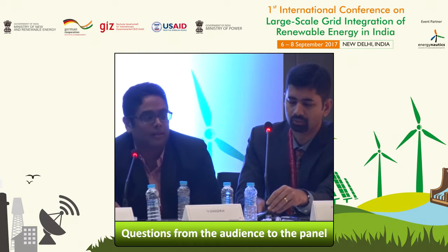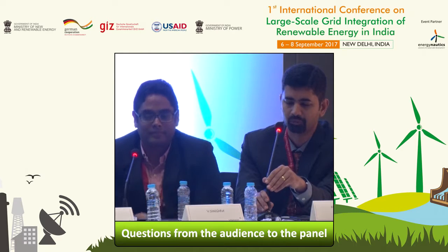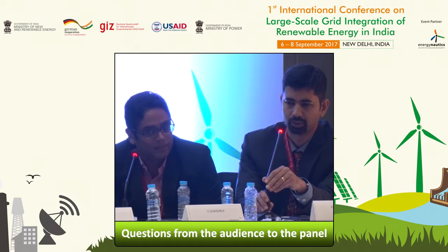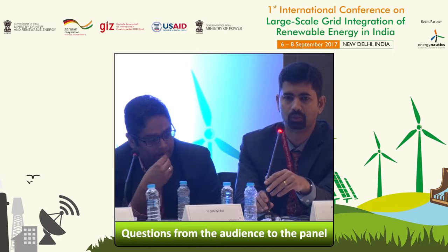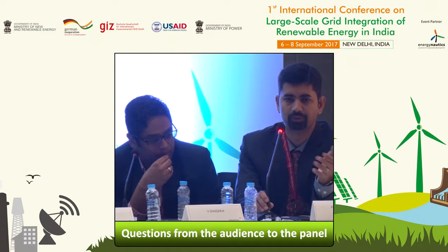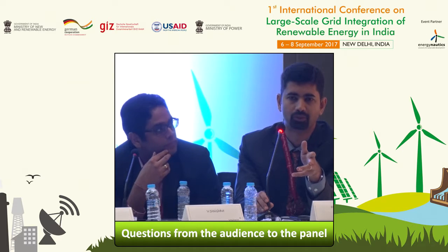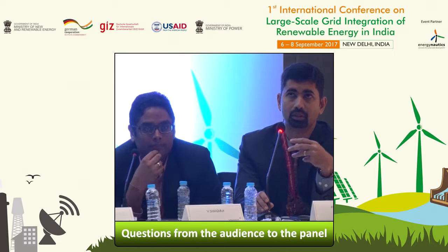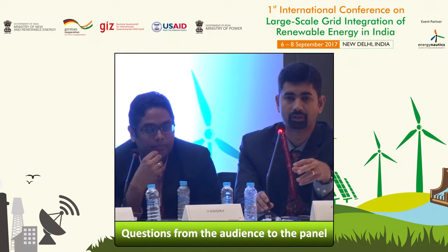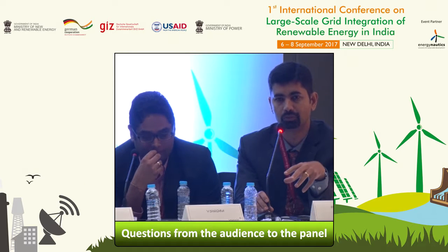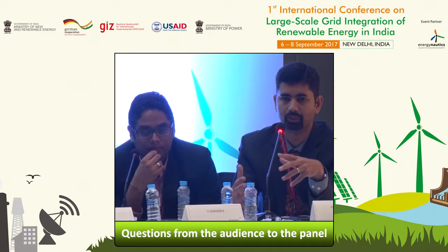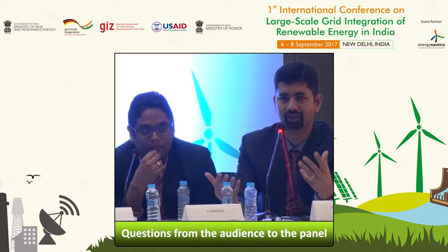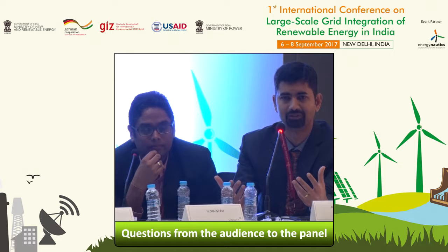Yeah, there's actually a regulatory requirement, I'm not exactly sure who it applies to, but I think it applies to MISO as a reliability coordinator or planning coordinator, that every 5 years we have to perform a small signal stability assessment. It's completed as part of our regular planning process. We've not initiated a separate study, because our wind penetration, even though the absolute scale is pretty large, 16,000 megawatts is not small, on a relative scale we have a 190,000 megawatt generation fleet. So percent penetration is still pretty low, less than 10%.